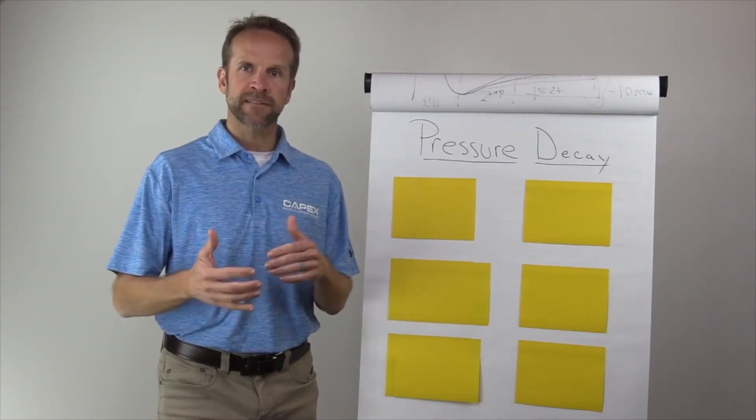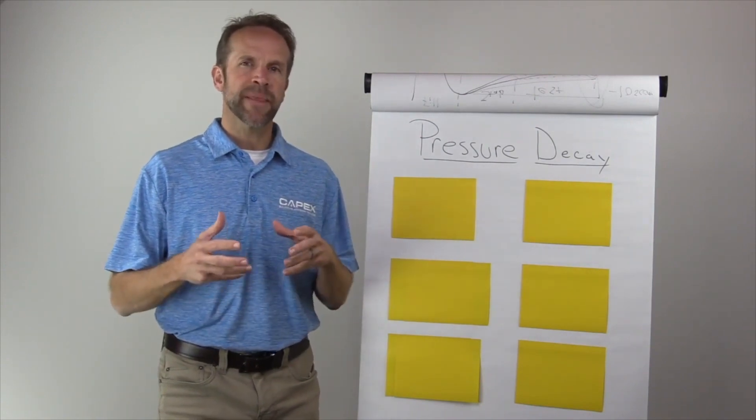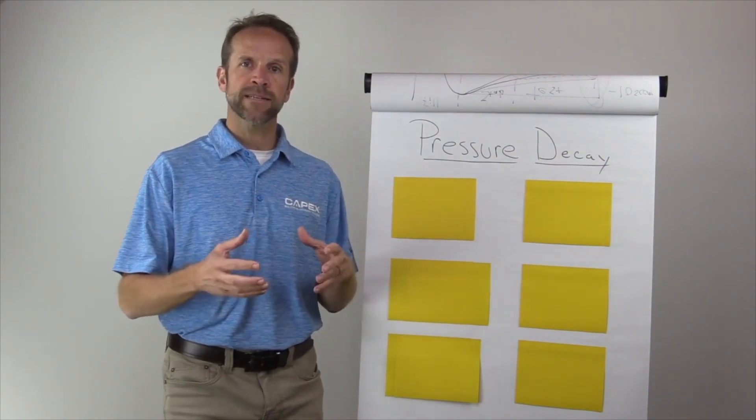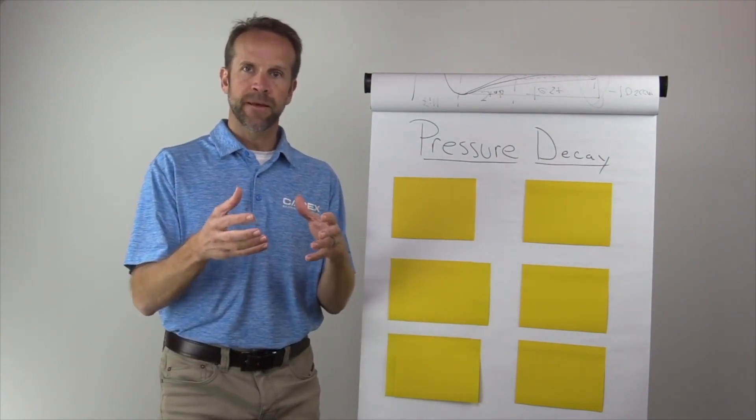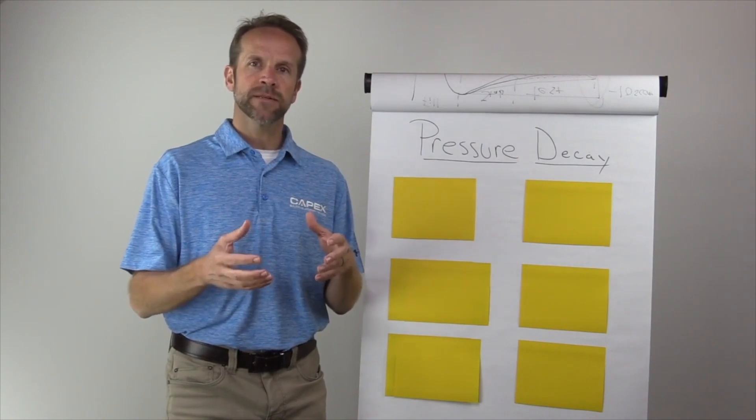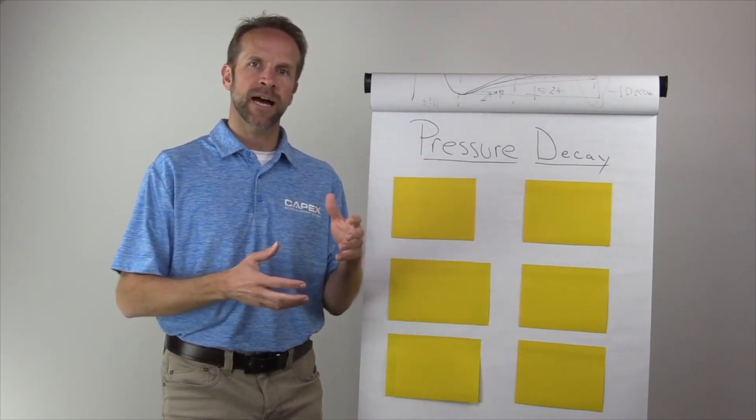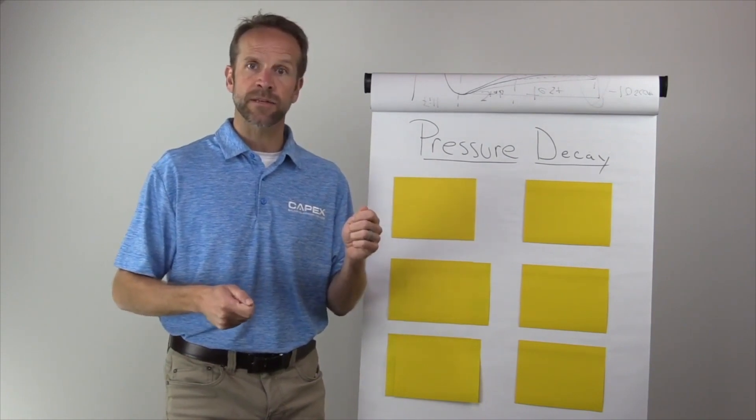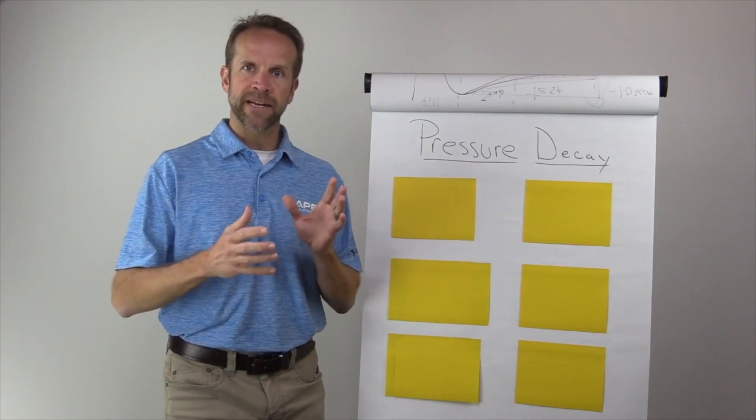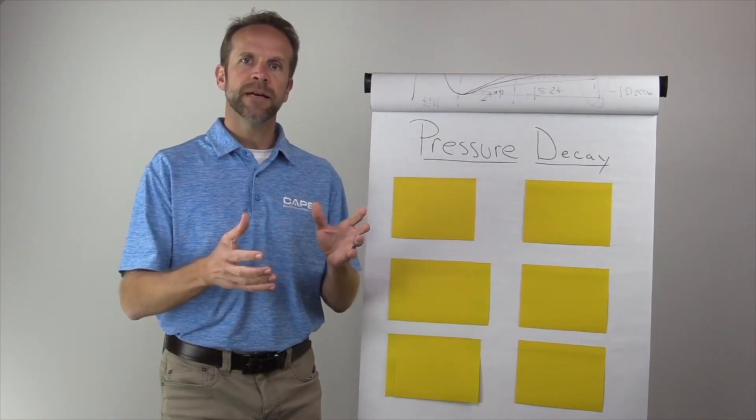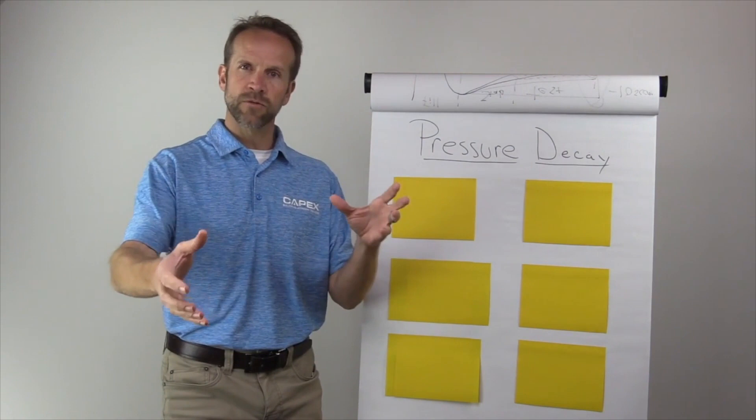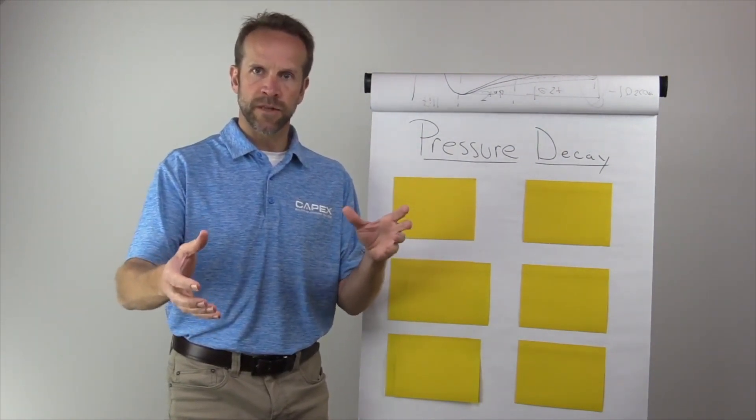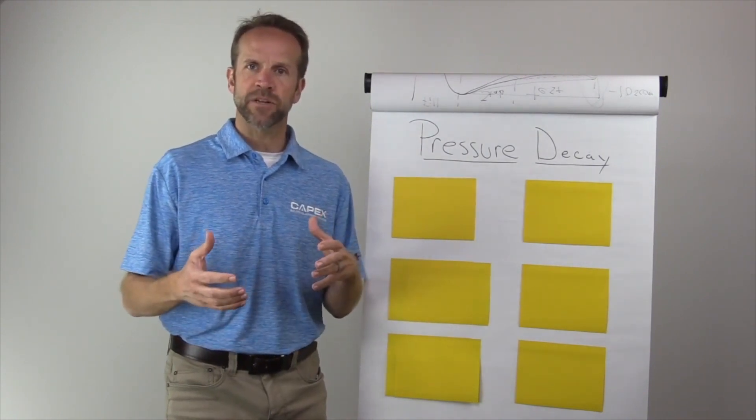With pressure decay leak testing, first let's talk about the definition. Pressure decay is measuring pressure loss over time. We're pressurizing a volume or your test part and measuring the pressure loss over time. What that means is theoretically you could isolate the test circuit. You could disconnect the air pressure going into the instrumentation and the test would still run because you've got a closed circuit where we are measuring the pressure loss.